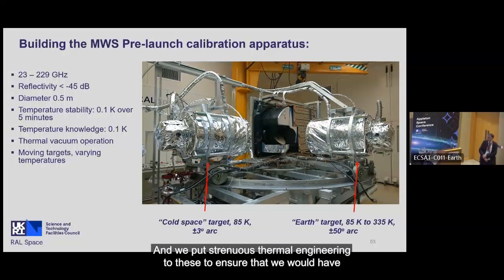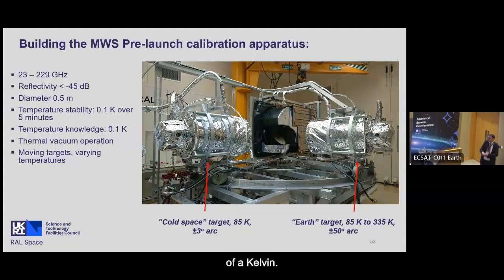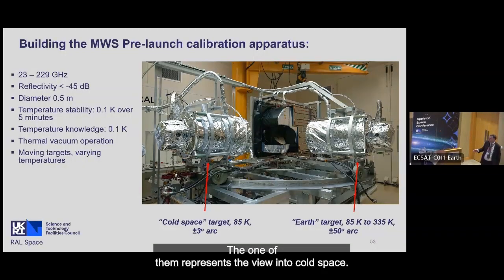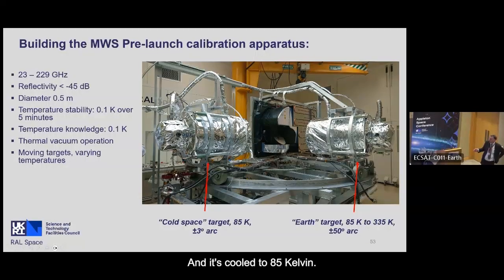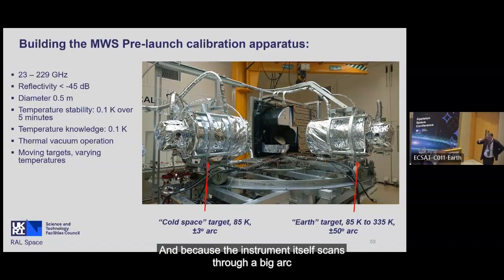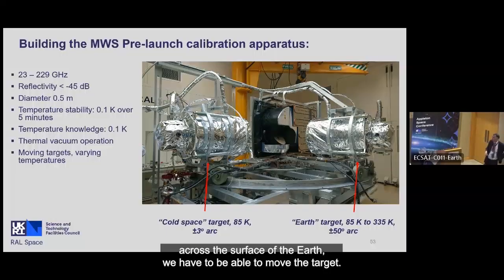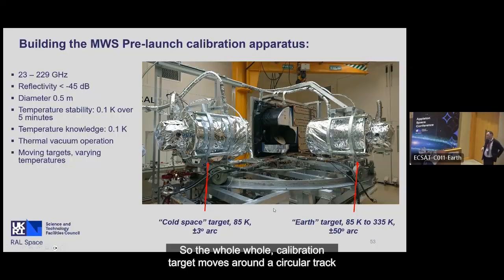And we put strenuous thermal engineering into these to ensure that we would have temperature uniformity and temperature stability at the level of 1/10 of a Kelvin. One of them represents the view into cold space, and it's cooled to 85 Kelvin. It doesn't move around. The other one represents the Earth view. It's variable in temperature, between 85 and 335 Kelvin, a bit over room temperature. And because the instrument itself scans through a big arc across the surface of the Earth, we have to be able to move the target. And you can just see the wheels here, so the whole calibration target moves around a circular track.